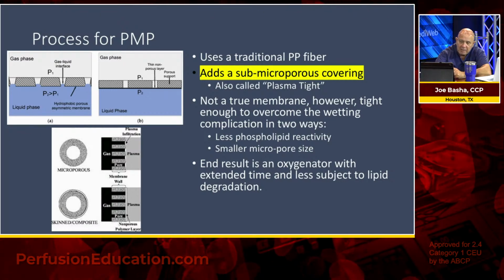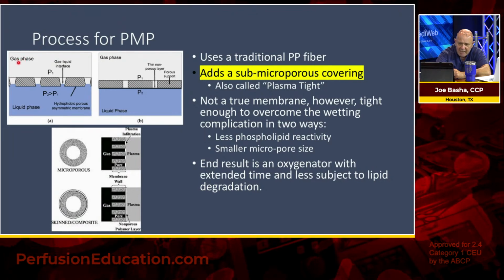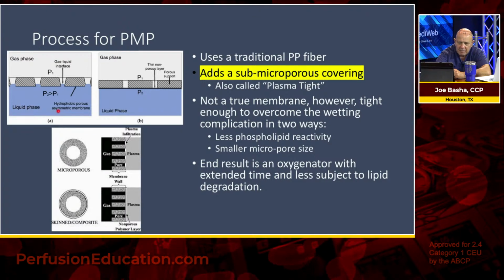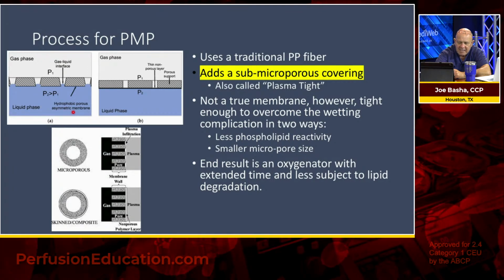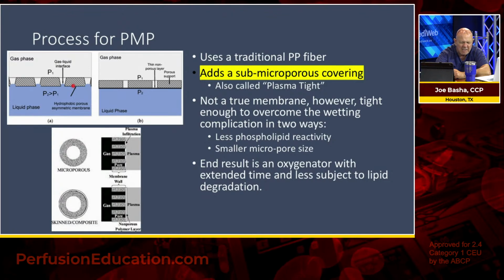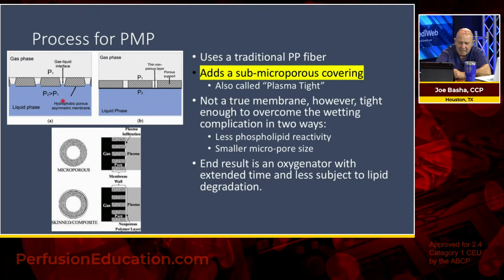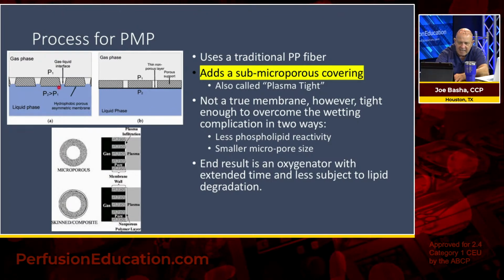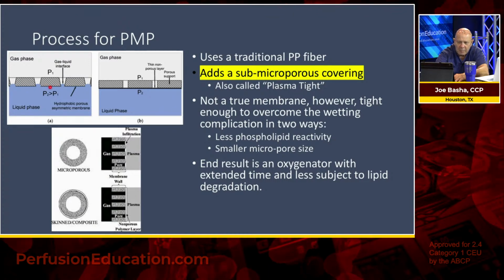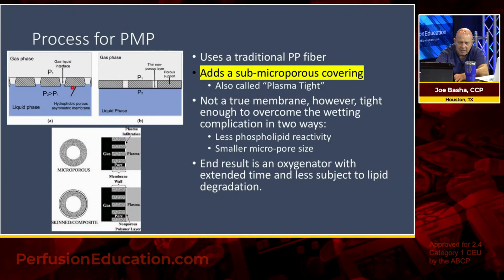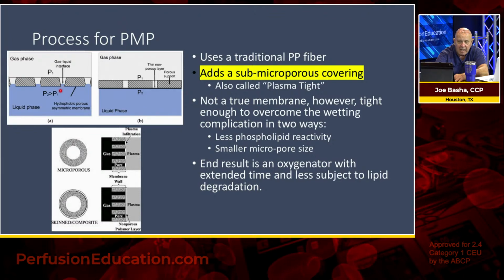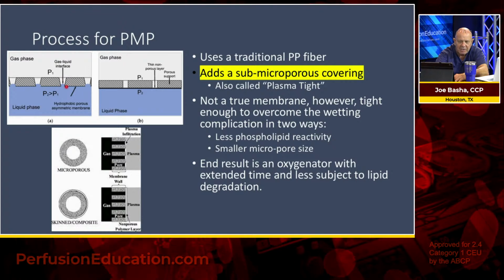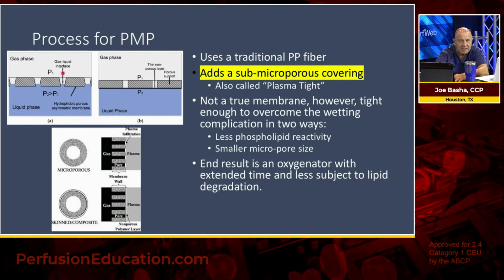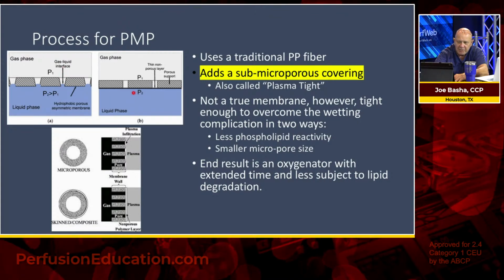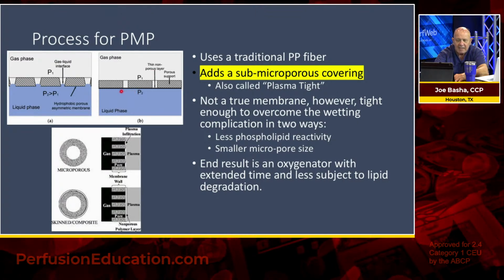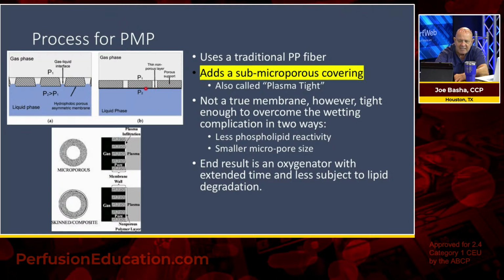So if you look up here on the top left, you have in the white area the gas phase. You have down here a liquid phase. You have the hydrophobic porous asymmetric membrane, which is this material here, which is really not a membrane, but is basically your hollow fiber. And you have a liquid phase. And you can see here in this section, this is normally hydrophobic, right? This section right here and here. But if you had lipids adsorb, which are hydrophilic, and they start to swell, you can see how this would start to distend and become larger, allowing the plasma to leak out from the liquid phase to the gas phase. Here you see this non-porous layer, which again, is submicroporous in my view, but you can see how it separates the two.